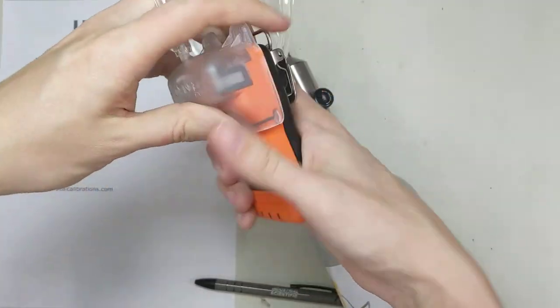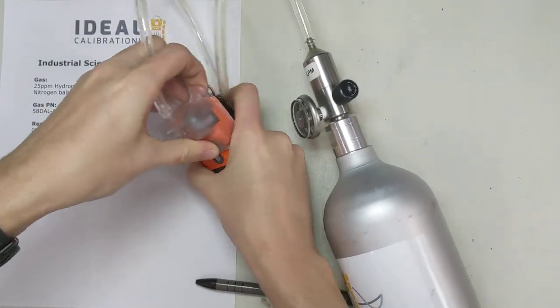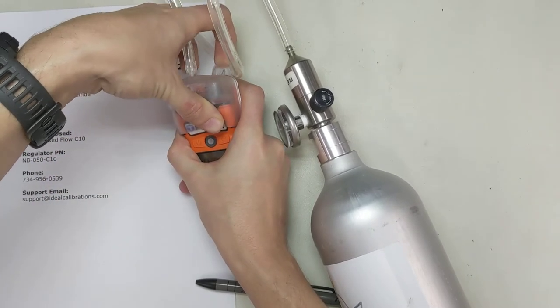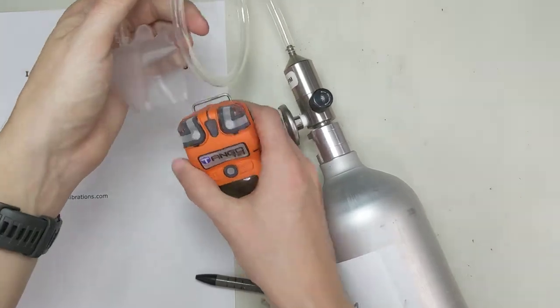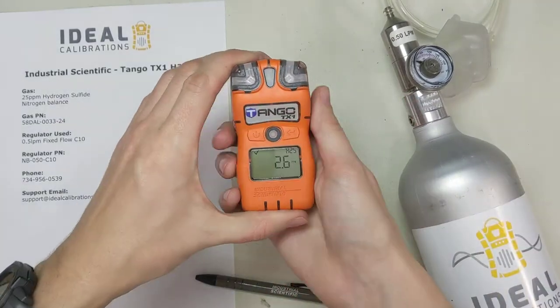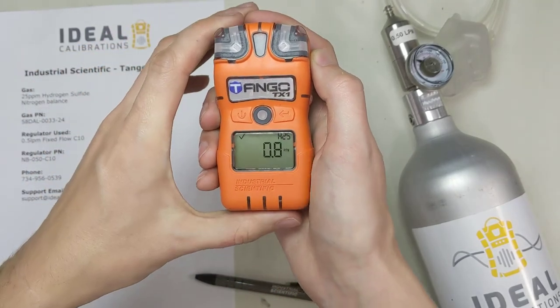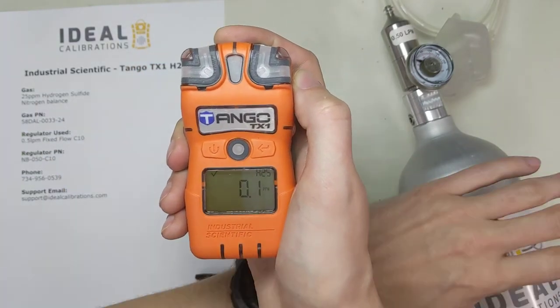Now we're going to pop the top off the gas. This calibration adapter isn't always easy to remove — the easiest way is to put it down on the ground, get a good grip, and instead of pushing on the tips, push right back on the back of the case and pry it up. That should pop it off a little bit easier. That's the calibration procedure. You can see the unit is bringing the reading back down now. On that sensor response — if it doesn't make it up to 25 where your calibration gas is, it's probably time to order a new sensor or check the gas.